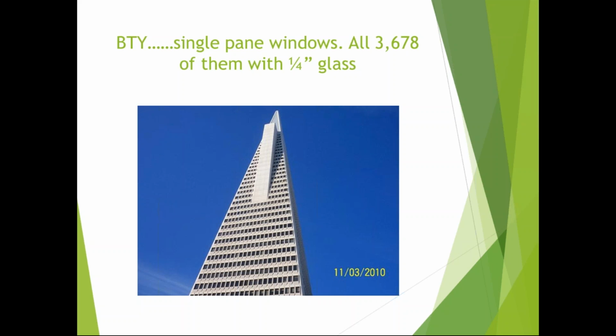It's an interesting experiment, because we know when the sun comes out with no wind versus when the sun comes out and there is wind, washing the windows, our tonnage goes up and down — you kind of know that. And when it's cool, cloudy, then sunny, then cloudy again, you see the equipment ramp up and down. The solar intensity on the windows, measured with a temp gun, is around 110 degrees at times, and you've got a tenant maybe 3 feet away from that glass.